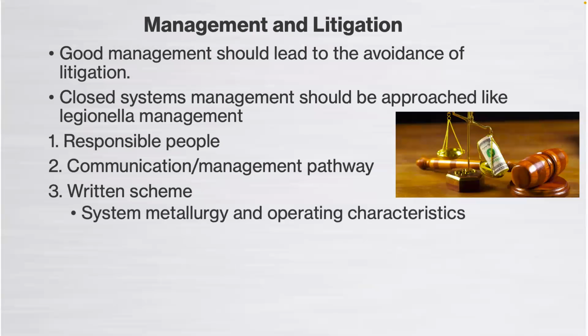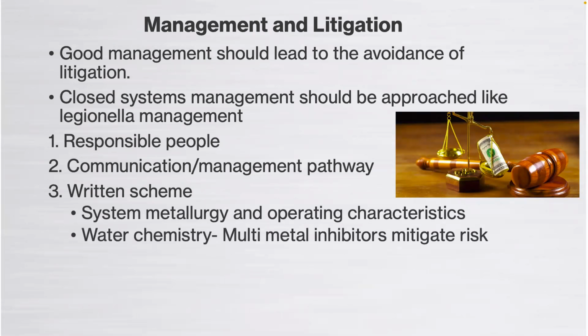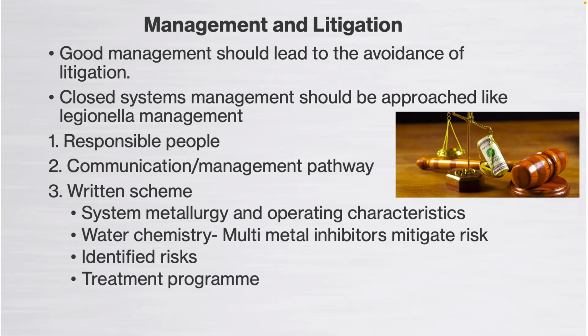Cover the types of metals on the system and the operating characteristics. So again, that avoids us putting the wrong chemicals in the system. Water chemistry, multi-metal inhibitors, so really covering all metals, and pH neutral, to mitigate risk. We need to identify any risks. That can be down to a controls philosophy that could lead to stagnant conditions in the system, for example. A treatment program, and of course, good record keeping. And nowadays, with everything on the cloud and a lot of data, there's no reason why it shouldn't be inputted into something like an Excel spreadsheet that then produces graphs. Water treatment is very much about science. Science is very much about trends. So if you're measuring levels of dissolved iron or total iron or copper, you can see and track whether you have an increasing trend. So that's really important.